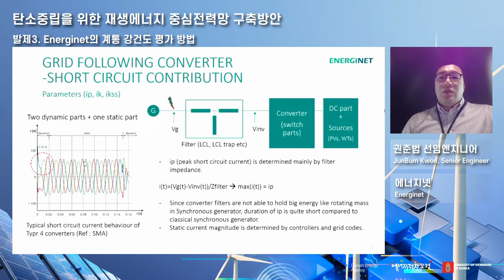Now diving into the methodology, 2 to 3 years ago we always applied the classical IEC methodology, which is the planning, correction factors, etc. We've done that, but now we are applying the complete methodology. It is based on the German grid code, and the complete operation scenario is based on the load flow instead of correction factors, and inverter-based generation uses different iterations to determine the contributions. We have different time frames used to measure short circuit current characteristics in the EMT model, where IP is the short circuit surge current, IK'' is the sub-transient short circuit current, and IK is the steady state short circuit current, with test conditions for short circuit current characteristics of VSCs in the EMT tool, test conditions for WTs, and test conditions for HVDCs.